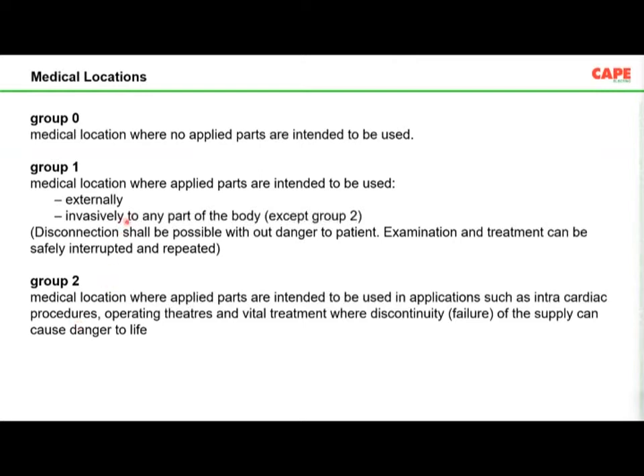Now, group 1 means a location where medical equipment is used externally, the applied parts are used externally, and group 2 means the applied parts are used internally, meaning sometimes the skin is bypassed and the equipment goes into the body. As I said, once the skin is bypassed, the resistance of the body is quite low, so you have to be very careful.